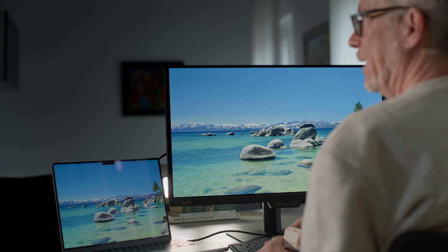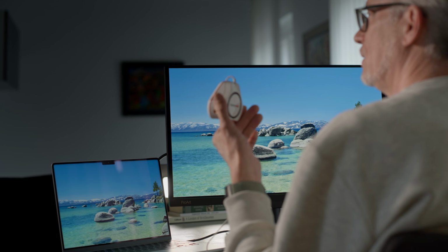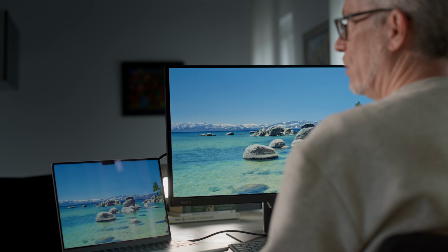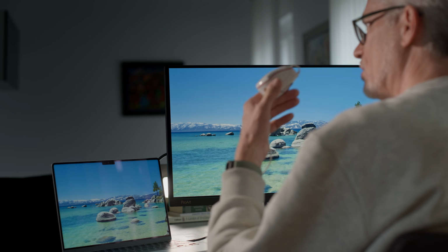My main objective for today is to test the color calibration of this monitor, again using my trusted Datacolor Spyder Pro colorimeter. But we also have to mention that you typically would not need this device to recalibrate your monitor because it has a built-in recalibration. And first let's do the following. We'll do the internal calibration of the monitor itself and then check the results using the Datacolor Spyder Pro.